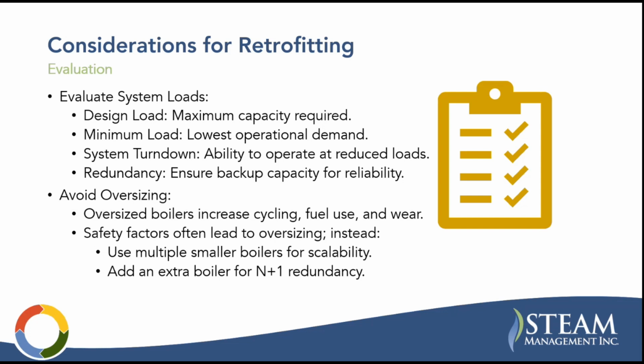capacity, and that boiler capacity will fall between two manufacturer model capacities, and then you pick the next one up, and pretty quickly you're oversized by 20% on your boiler. So you want to avoid that, and maybe consider just picking the smaller boiler and adding an extra boiler for that N+1 redundancy. And these boilers actually work pretty well together, so that's a good strategy when you're picking the sizes.